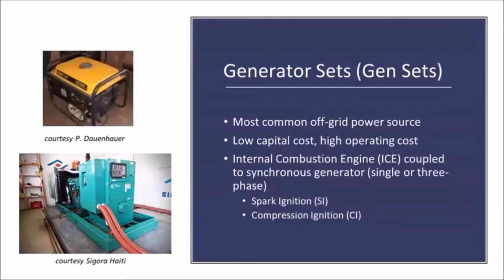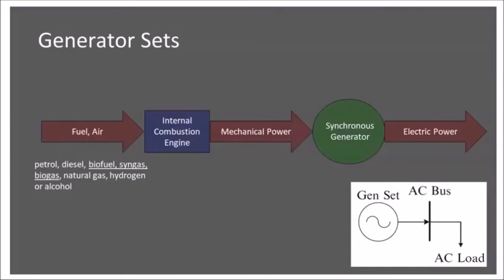There are a few different types of gensets depending on the nature of the internal combustion engine — spark ignition, as in a petrol generator, or compression ignition, as in diesel. The basics of how a genset works: we feed fuel and air into an internal combustion engine. After combustion, we get mechanical power on the engine's crankshaft, which is coupled to the generator's rotor. Rotating that rotor provides electrical power when connected to a load. Because we can regulate the flow of fuel and air, we can control the speed and directly couple the genset to an AC load.